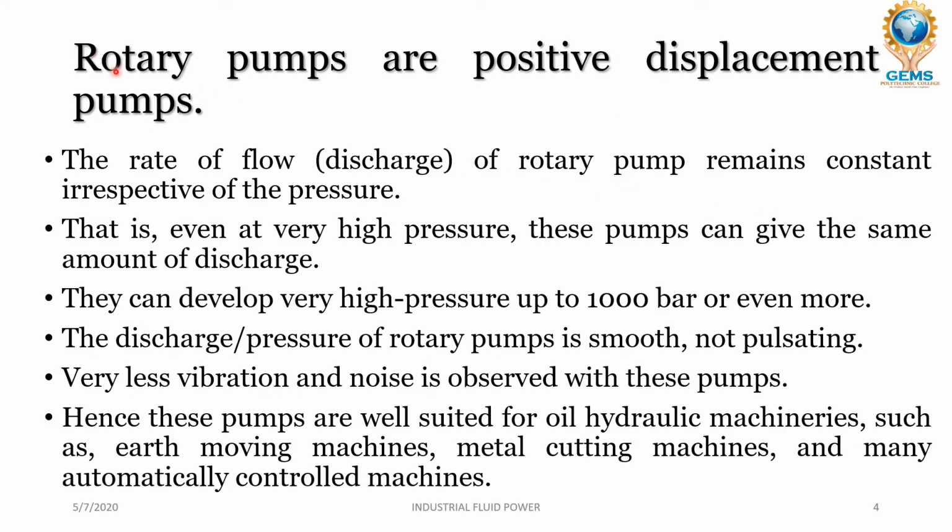Let's see what the rotary pumps are. Rotary pumps are positive displacement pumps. The rate of flow, meaning the rate of discharge of a rotary pump, remains constant irrespective of the pressure. Even at very high pressure, these pumps can give the same amount of discharge. They can develop very high pressure up to 1000 bar or even more.